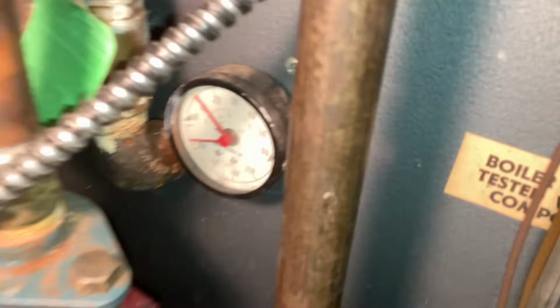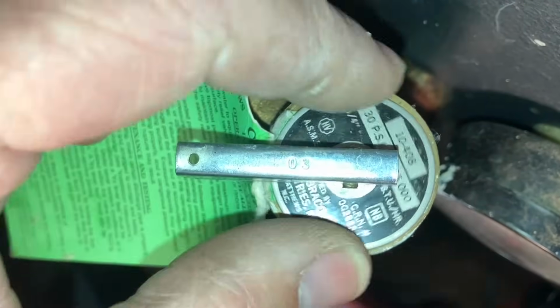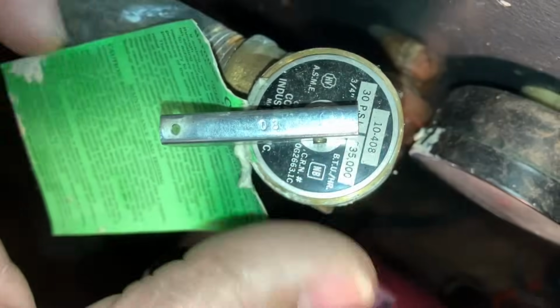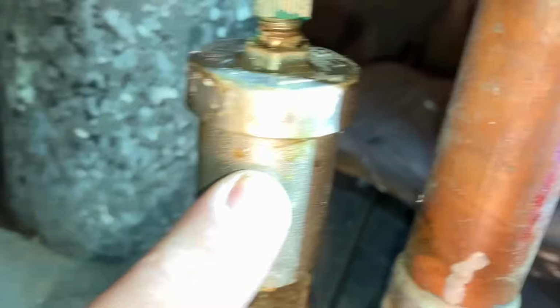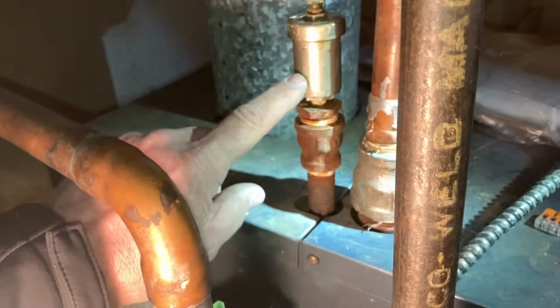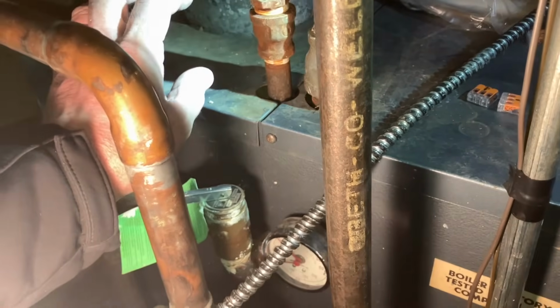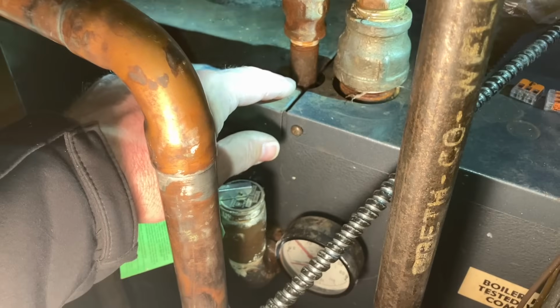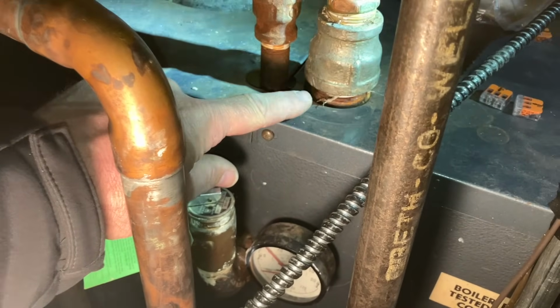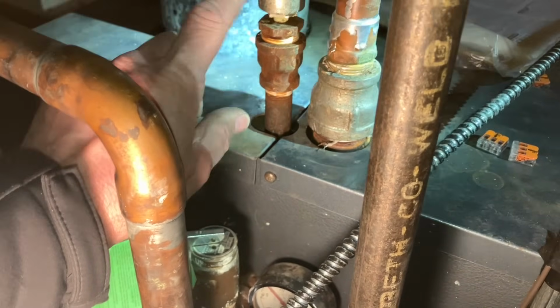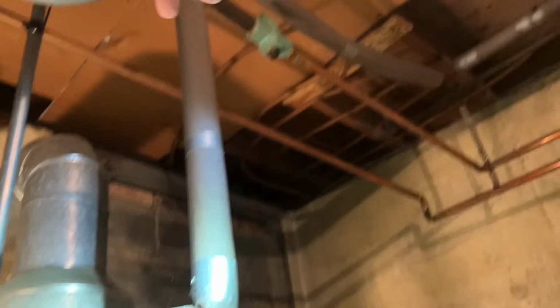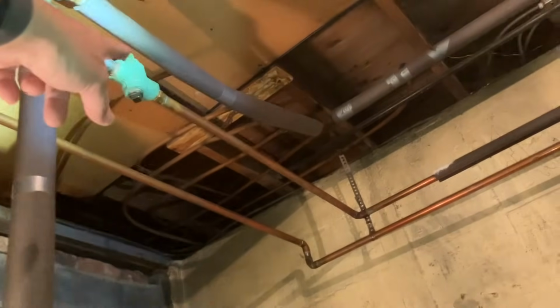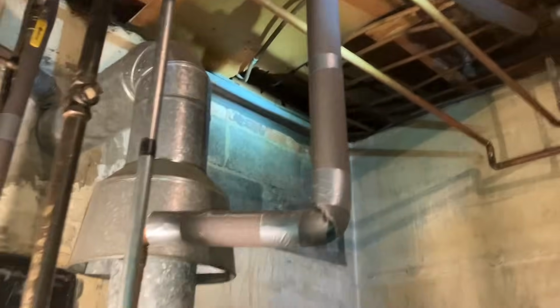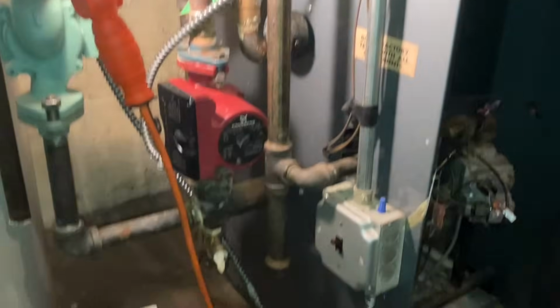Yep. So let's take a look at some components here. Right here is our relief valve. This should be a 30 PSI relief valve, and it is. Okay. This is an automatic air valve. Weil McLain, this model, which has been replaced by the CGA, always has that 1/2-inch tapping right next to the 1 1/4 coming out of the top of the boiler. That's for your automatic air removal. Coming out of the top, you have 1-inch copper, and then it goes into 2 zones here. 1 3/4, 1 1 inch. The 1 inch is your main zone. The 3/4 was an addition later on.